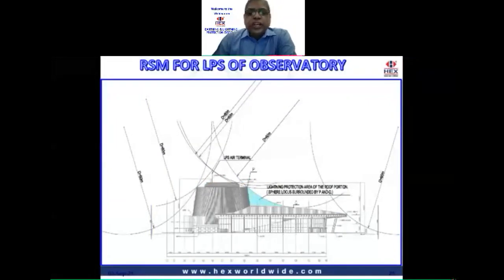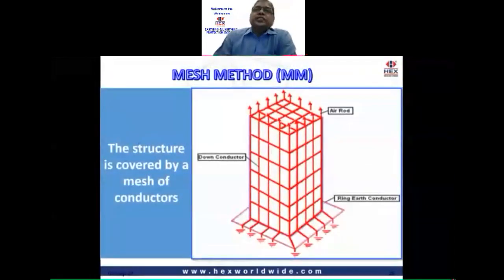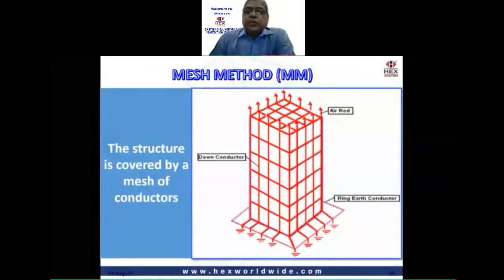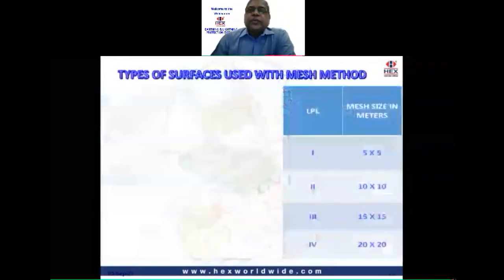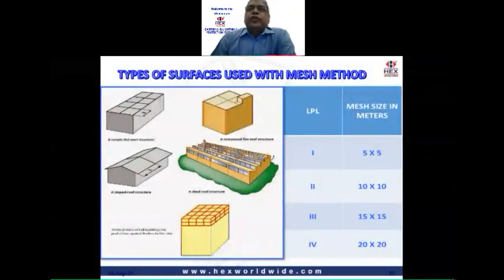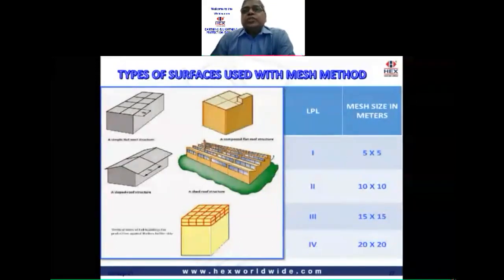Now, moving on to the next method, which is the mesh method. This states that the entire structure should be covered with a mesh of conductors, with lightning arrestors and down conductors placed at specific locations. This method is generally used for flat roofs; for tall buildings, the sides also have to be covered by the mesh. The size of the mesh to be used is given for all four lightning protection levels. So for the first level, the square will be 5 by 5, as shown in the drawings, and so on and so forth.